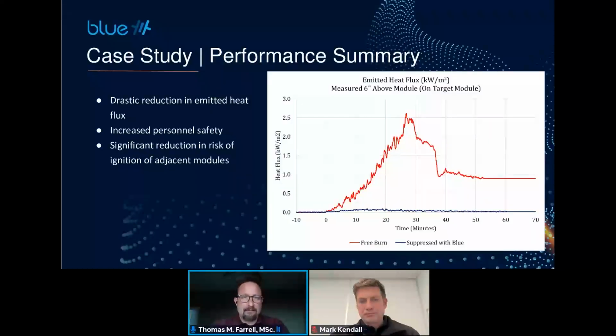But that is sustained heating of everything around it, which means it's additive heat to the neighboring modules, which means it becomes very likely that something nearby would also go into thermal runaway just because this one went into thermal runaway. We see this as a huge win from the standpoint of personal safety, keeping first responders safe if they have to get close to it, or if it's already open to the atmosphere or accessible. It brings it down to a level where, given the right safety protocols in place, it is possible that this module could have been extracted from the rack pretty early on in its process and then set aside, guaranteeing that there was no chance that it could cause continuing propagating thermal runaway inside of another pack.